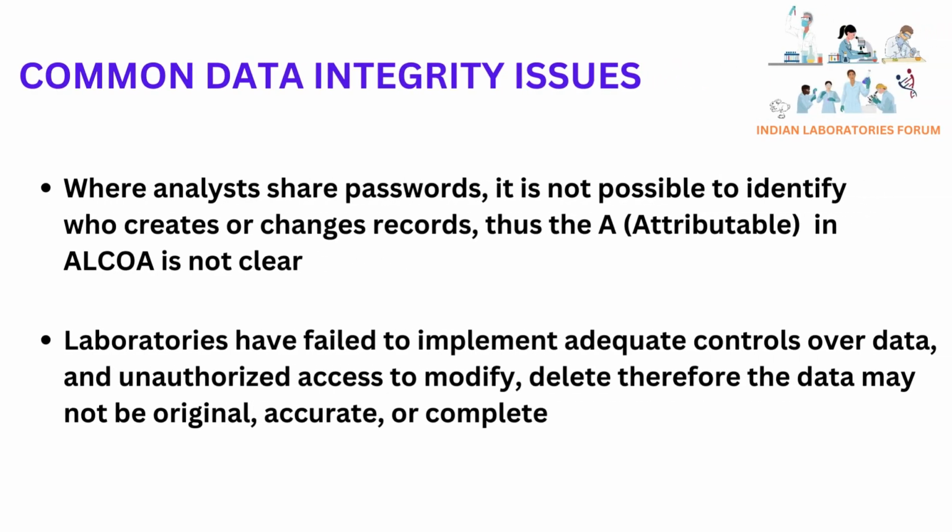Common data integrity issues. Below are commonly identified data integrity issues in different regulatory inspections. Common logins or sharing login passwords. It is not possible to identify who creates or changes records, thus it is not attributable. Laboratories have failed to implement adequate controls over data, and unauthorized access to modify or delete, therefore the data may not be original, accurate, or complete.